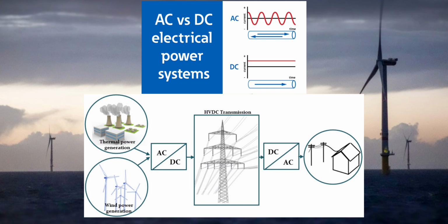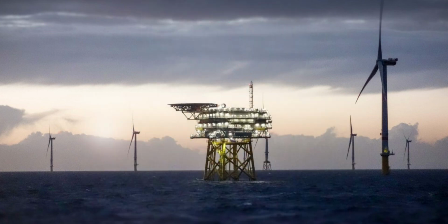In AC transmission, alternating waves of voltage and current travel in the line, which change direction every millisecond, due to which losses occur in the form of heat. Unlike AC lines, the voltage and current waves don't change their direction in DC. HVDC lines increase the efficiency of transmission lines, due to which power is rapidly transferred. In a combined AC and DC system, generated AC voltage is converted into DC at the sending end. Then, the DC voltage is inverted to AC at the receiving end for distribution purposes.